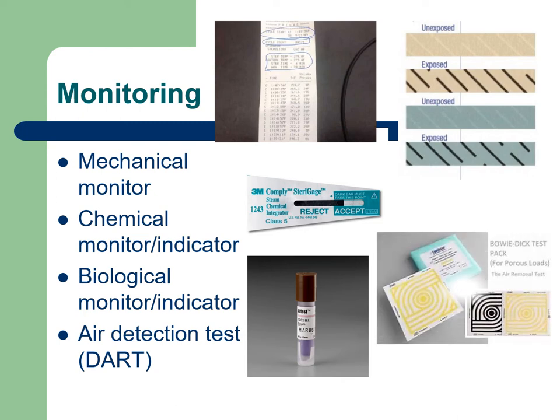The last thing is a monitoring test, a detection test called the Bowie-Dick test. DART stands for daily air removal test. When we use a steam sterilizer, one of the things that happens is that all of the air gets pushed out of the chamber before the steam comes in. So we want to make sure it's working properly and removing all the air. That's why it's an air detection test.